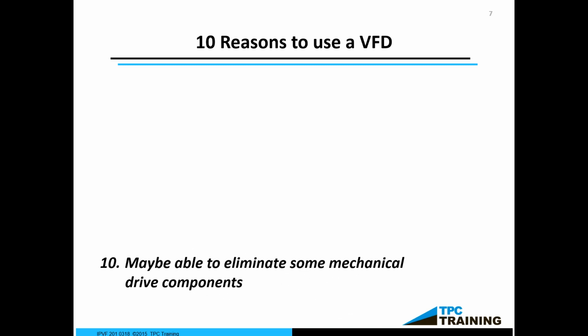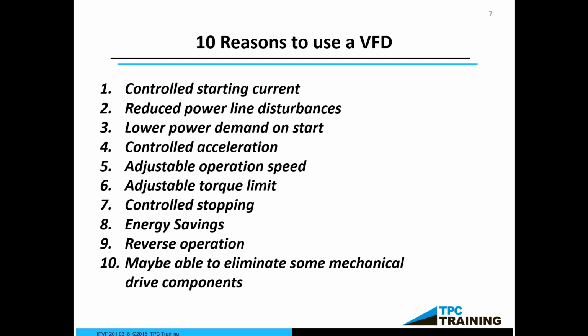Perhaps you don't have a drive at all. You want to change over from a mechanical system. You'd have to do some torque calculations, and there are calculations that we can use to calculate torque based on motor speed. So we'd have to convert or size a drive specific to your particular application. A lot of reasons, and there are even more reasons.